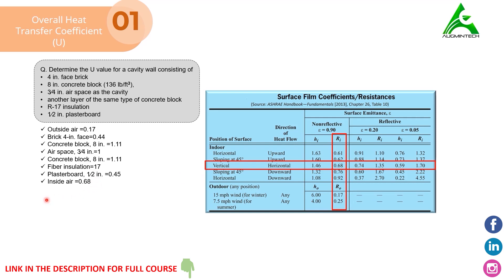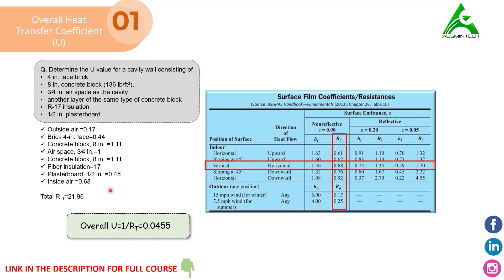These are the resistances of the individual components used in the construction of the wall. To get the total resistance, all values are added together. Then, using the formula U = 1 / total resistance, the value of U is finally found to be 0.0455. This is how we determine the value of U for a wall.